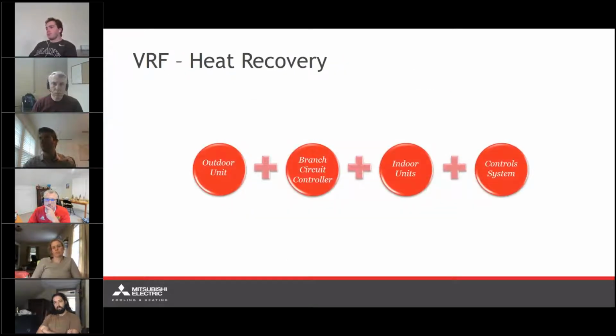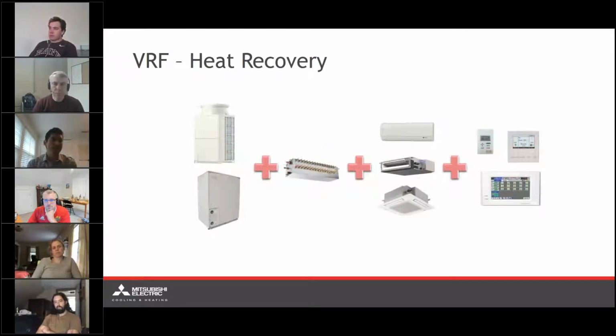So going back to my little button overview here, the branch circuit controller, shown graphically here, has 2 pipes of a refrigerant network connecting our outdoor units to our branch circuit controller. And then the heat exchange process occurs within the BC controller itself. Then each fan coil or group of fan coils connected downstream of the branch circuit controller, every port is individually going to be supplying heating or cooling as is requested by the zone. So ultimately, that was just a quick overview of what VRF systems are and a top-level overview of the difference between our heat pump and our heat recovery systems.